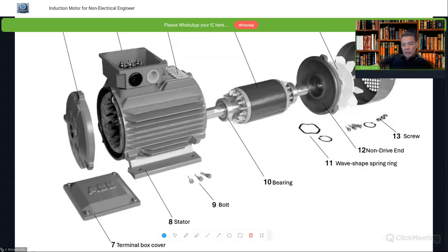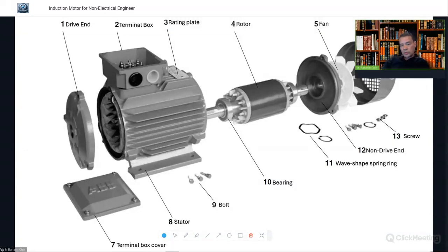So normally, induction motors are divided into two. One is the LV, which is the low voltage motors. The other one is HV motors, that is high voltage motors. LV motor voltage will be 400 volt and 415 volt. And then according to the IEC, HV motors will be the ones that have greater than 1000 volt. In normal case, we could have 3.3 kilovolt motors, 6.6, 11 kV, and the maximum available motors that we have in the market is 13.8.